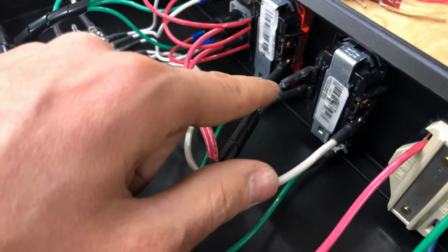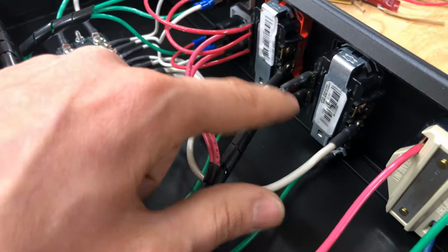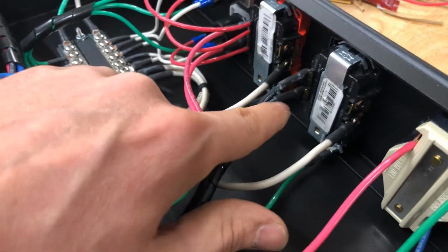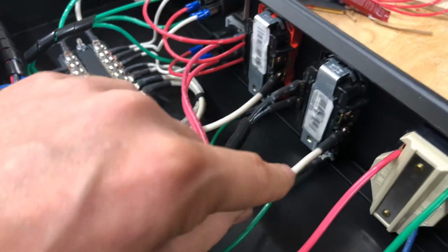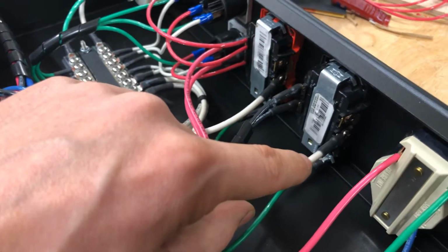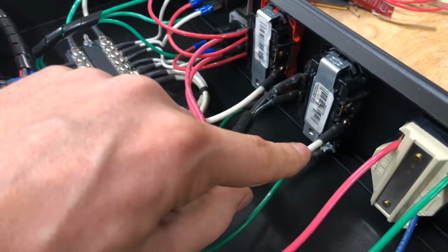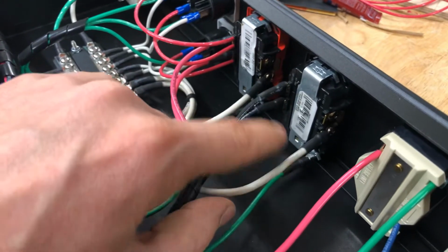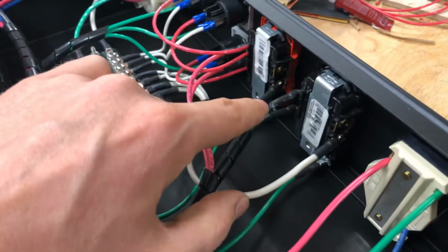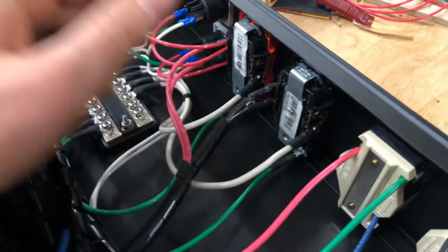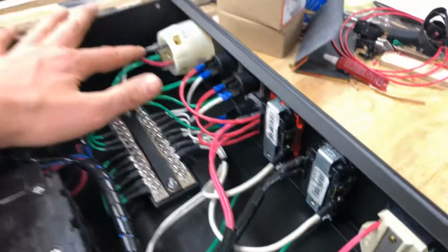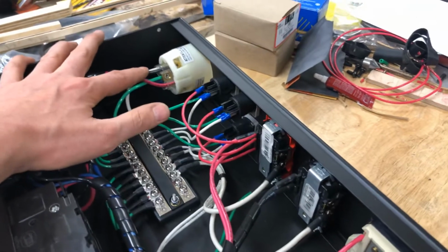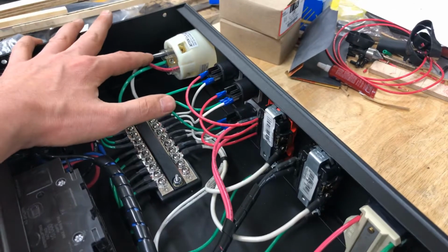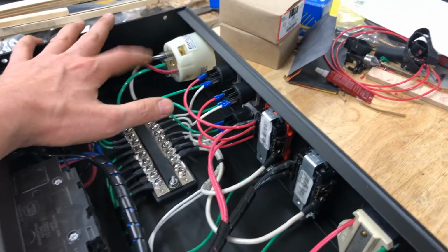So if, for instance, you had 15 amps on each one of these circuits, it would overcurrent this wire because they're on the same phase. Now, you can't possibly have more than 15 amps on each one of these, even though they're 20 amp circuit breakers, because the maximum potential of the entire system is 30 amps, since this is an L21-30 three-phase receptacle.